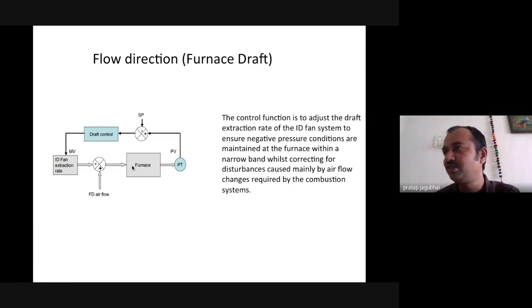Draft control is based on draft pressure, which I said is a PID based control, and you can put a lookup table for your feeding as well as your FD, so that it can respond in a better way. But maintaining a balanced draft near 0 mm, 0 mm draft pressure, is our prime objective for safety as well as efficiency. If we have a positive draft, it is an indication that FD is delivering more and there is a chance of backfire. So tighter draft control always ensures safe and efficient operation.